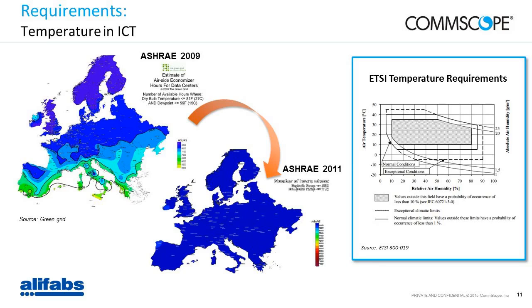in about the northern area of Europe. Well, 2 years later, the latest ASHRAE requirements meant that quite a lot of new sites could be running on free cooling. And again, this is for strategic sites, data centers. In the meantime, the ETSI standards are actually dictating that you can run your sites above 35 degrees as long as it's less than 10% of the year. So you probably heard that there's about 8,760 hours every year. So that means that for 876 hours every year, you can run your sites above 35 degrees.